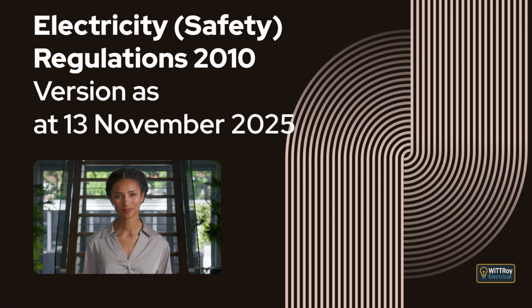Reg 87 prohibitions relating to fittings and appliances. This regulation explains that if WorkSafe reasonably believes a fitting or appliance is, or may be, electrically unsafe, it may prohibit activities such as manufacture, importation, sale, installation, or use of that fitting or appliance. It also explains that if an item is imported under the Conformity Cooperation Agreement but does not actually comply with that agreement, WorkSafe may prohibit its import, sale, installation, or use.